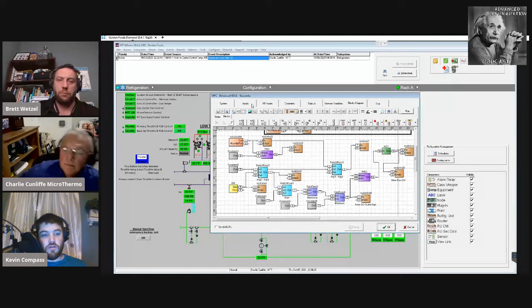All mine were in the 700 boards. So it's going to be in the block diagram here, the way this guy did it. I've never seen them in the block diagrams. All of ours were actually in the actual 700 board. You would go into the 700 board, and all the settings were inside of there. Once you opened up the little three lines and went into the setup of it, you could change the throttle range, the flash gas bypass minimum percentage, and all that stuff.